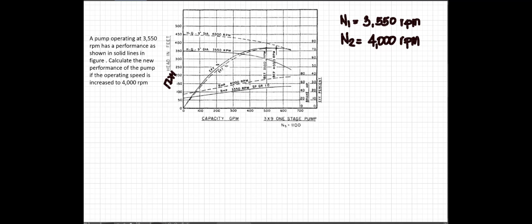Then, how do we read this chart? This is what we call the pump characteristic curve. Usually here you can see the properties of the pump. You will notice we have here the percent efficiency and where it runs along this line, then the corresponding brake horsepower, BHP, and your RPM. So this is what it says: 4,000 RPM, dash line, then the solid line, we have 3,550 RPM. Now, SPGR is the specific gravity of the fluid. When you see that it is 1, it means we are using water. The specific gravity of water does not change, it will always be equal to 1.